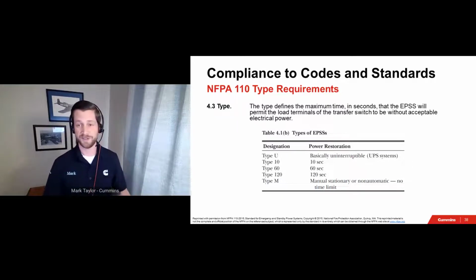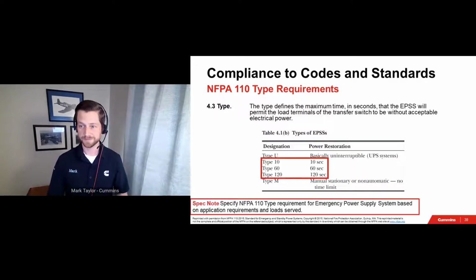So just like ISO 8528, it's just a performance-based standard. Of course, specify NFPA 110 type to fit the needs of your application and applicable codes and requirements. Do not let the start time requirements rule out a certain fuel type if both diesel and gaseous fuel generator sets can meet these requirements. So work with your generator set manufacturer for any help in understanding the options that you have available.